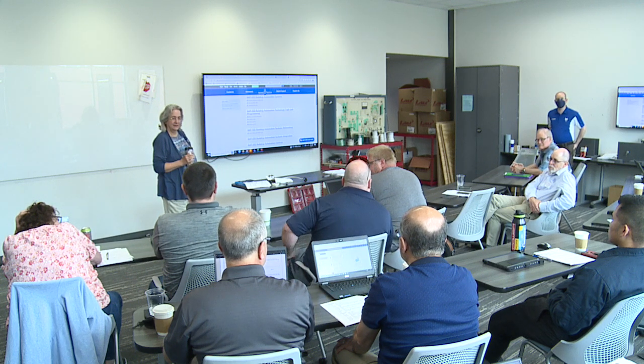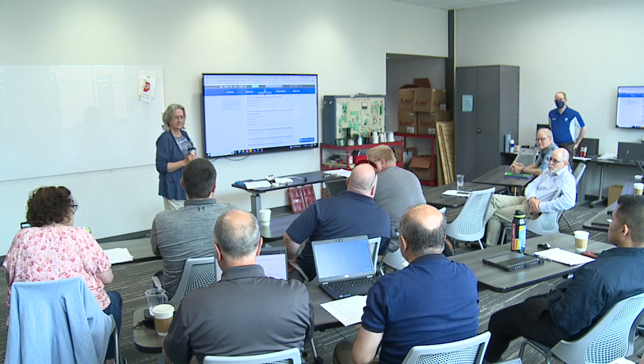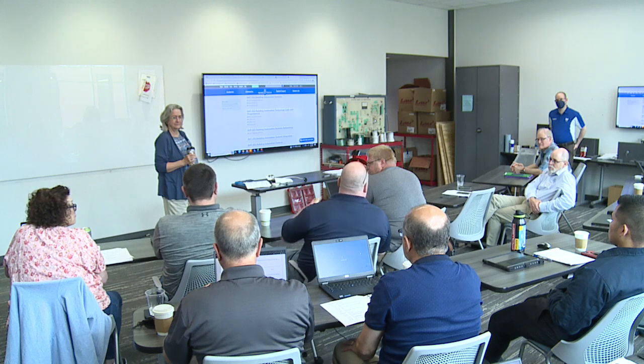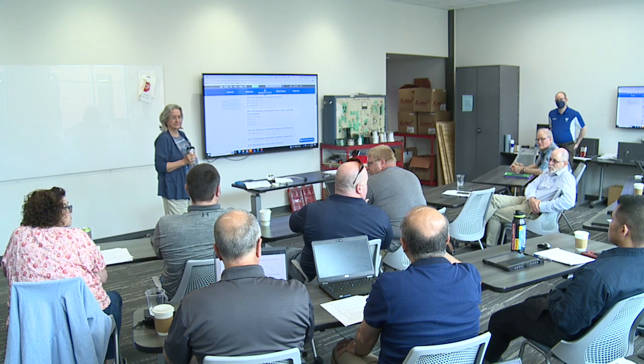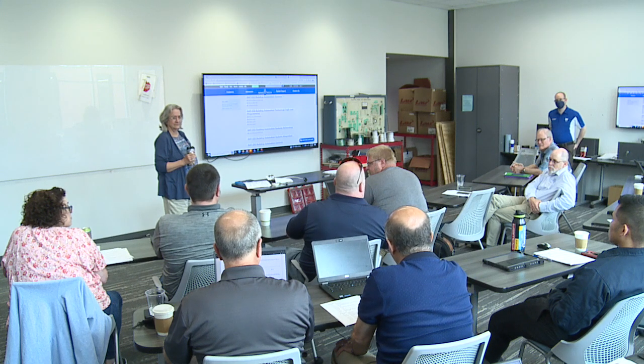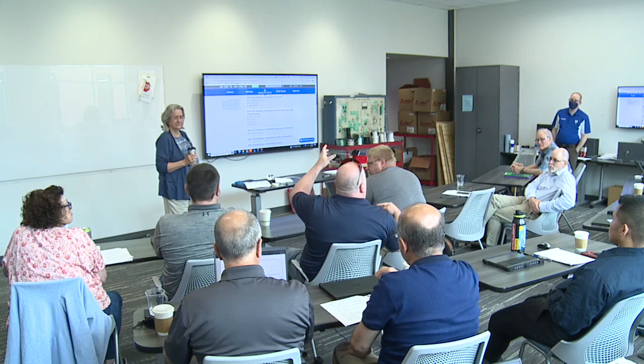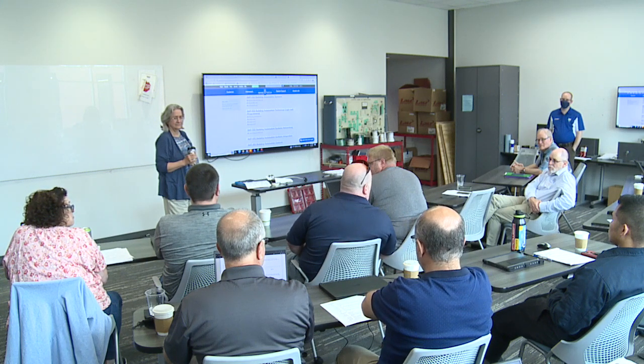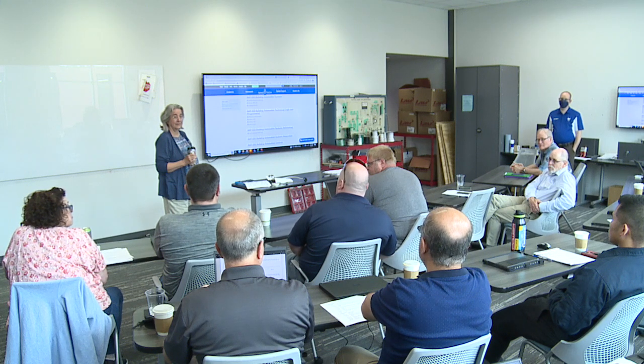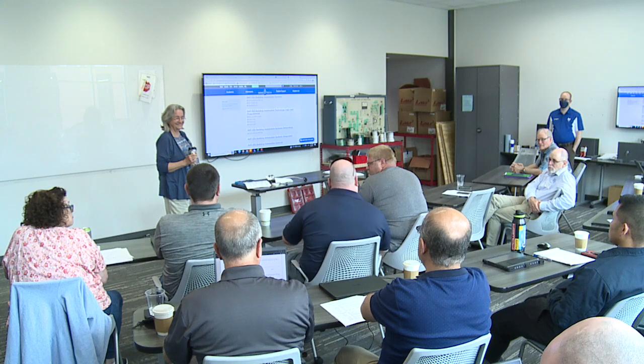That's from John Kepke out of Junior College, he did it with the PLC. Changed my whole perspective on that stuff. But an incandescent light bulb in the base, and you just get a toilet flange, flip it upside down, and then mount a light bulb under it. And then it can stand up, a 3-inch piece of PVC, and you can drill different holes at different levels and drop your 10K type 2 thermistors in it. It works out really well to teach PID loops. And it's simple, costs less. You can steal all the stuff from the plumbing department.